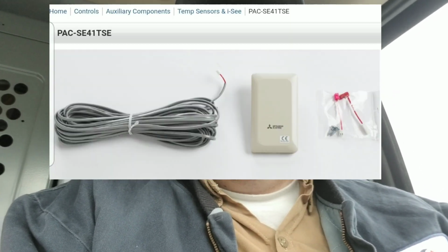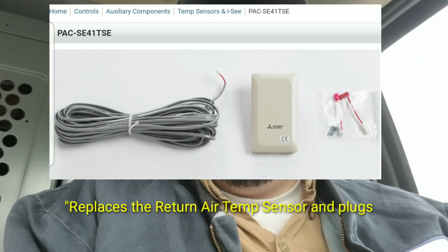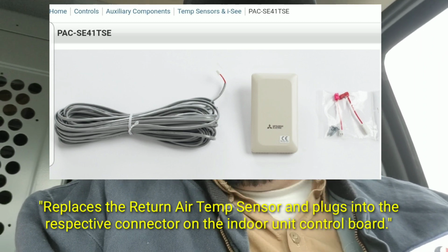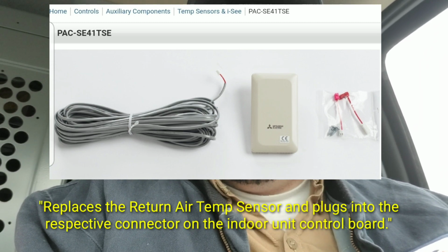This unit was freshly installed. In the previous application, it was running off a remote return air sensor. So Mitsubishi makes an accessory which essentially plugs into the same port as the return air sensor, but it comes with like a 50-foot cable so you can mount it somewhere else. So it's kind of like a stat, but kind of not. But so they had used that.